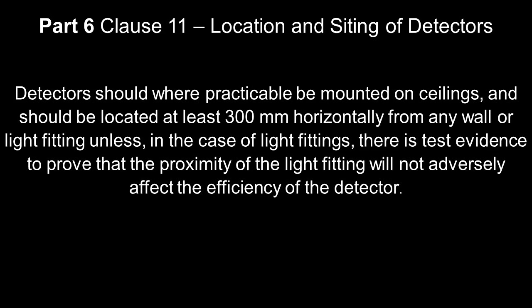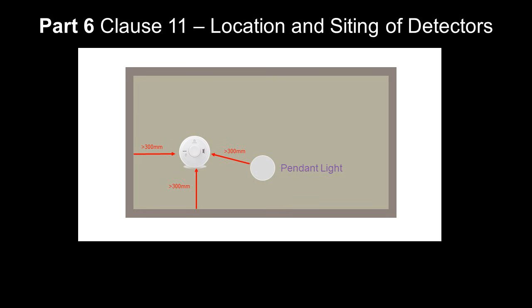Detectors should, where practicable, be mounted on ceilings and should be located at least 300mm horizontally from any wall or light fitting, unless in the case of light fittings there is tested evidence to prove that the proximity of the light fitting will not adversely affect the efficiency of the detector. Good luck with that, by the way. So basically, don't install them closer than 300mm to any walls or any light fittings.